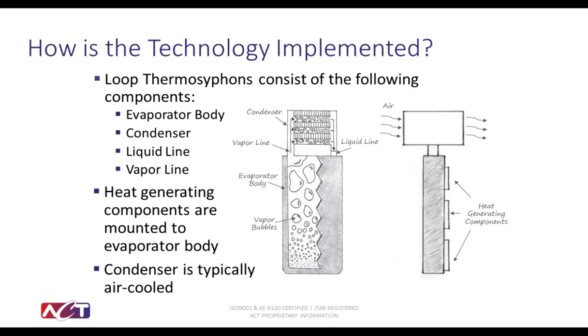In most of these applications, the condenser is air-cooled. However, we here at ACT think of this as an advanced passive thermal solution due to the concentration of that heat and the concentration of all your fan power. Having the fan power, having the heat sinks for these components distributed throughout a system will add more points of failure. In this way, by concentrating them into a single device, you're making use of this advanced passive transport to condense the back end of the solution.